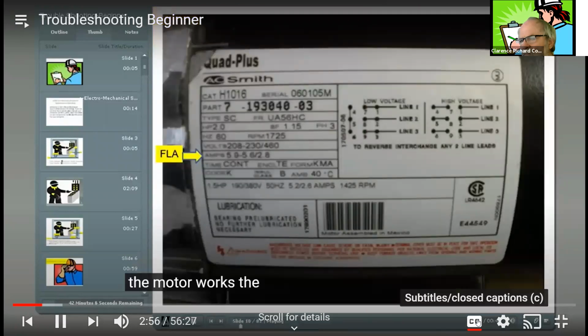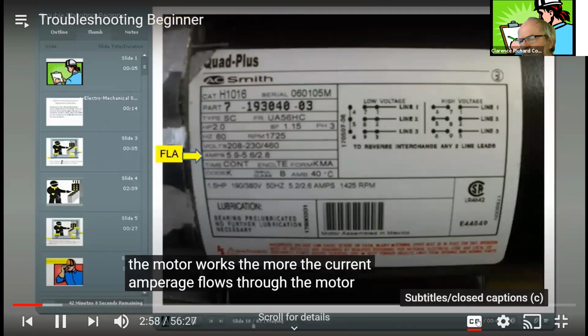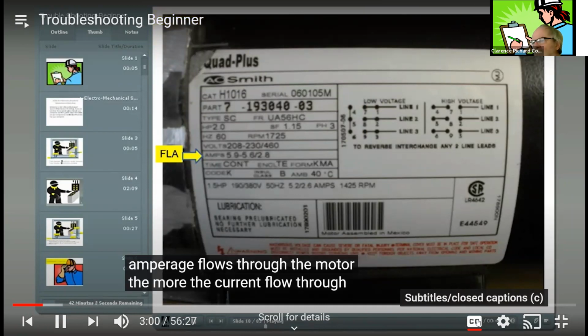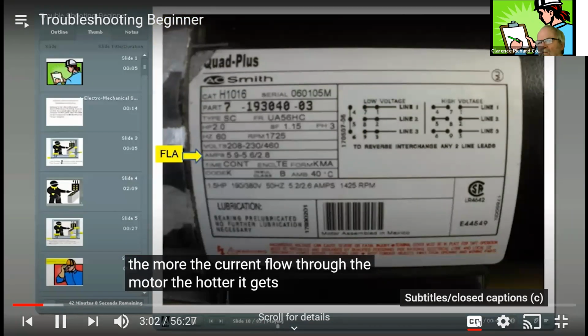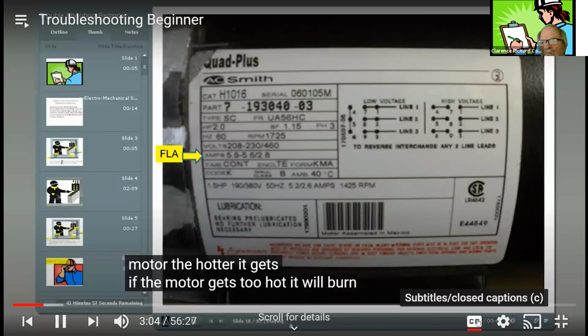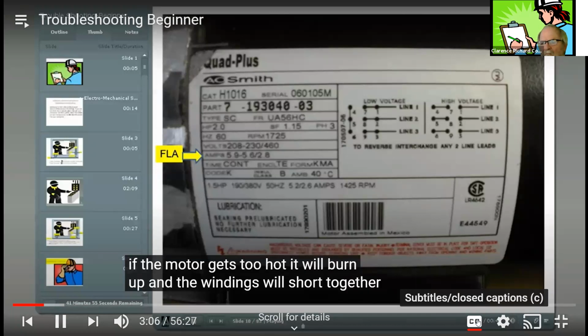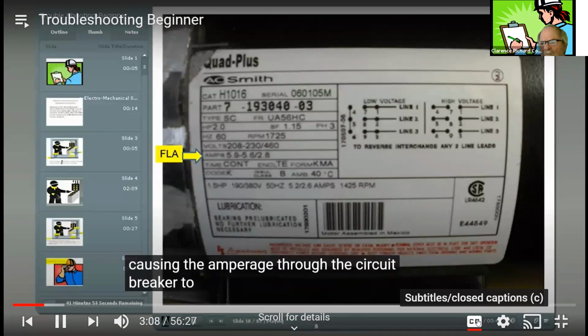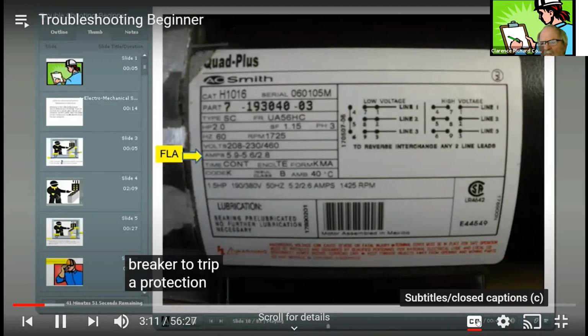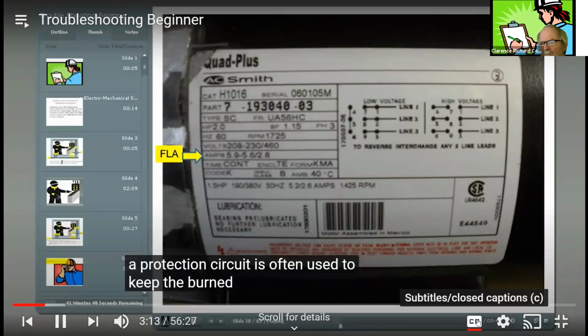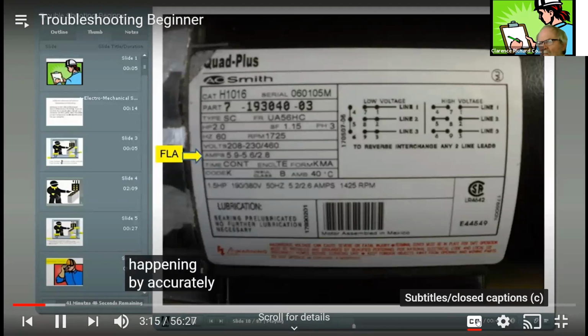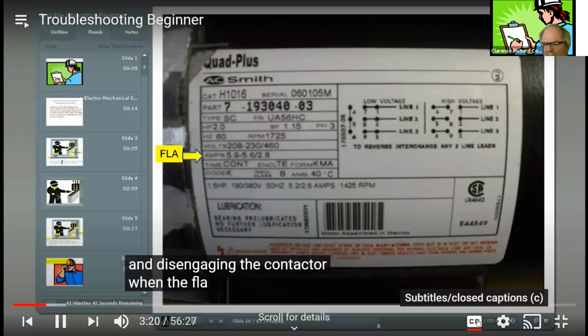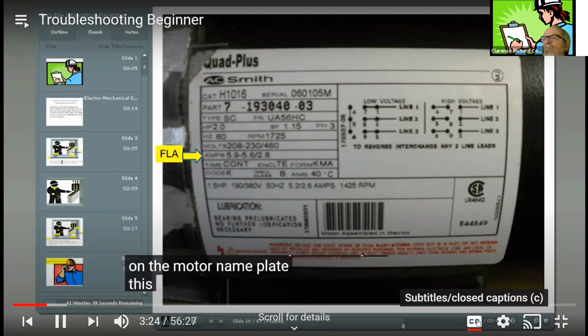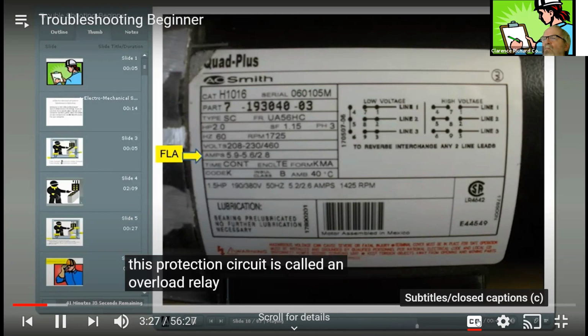The harder the motor works, the more the current amperage flows through the motor. The more the current flow through the motor, the hotter it gets. If the motor gets too hot, it will burn up and the windings will short together, causing the amperage through the circuit breaker to trip. A protection circuit is often used to keep the burned motor disaster from happening by accurately measuring the current flow and disengaging the contactor when the FLA, full load amps, as stamped on the motor nameplate, is exceeded. This protection circuit is called an overload relay.